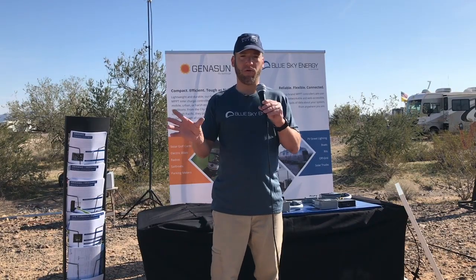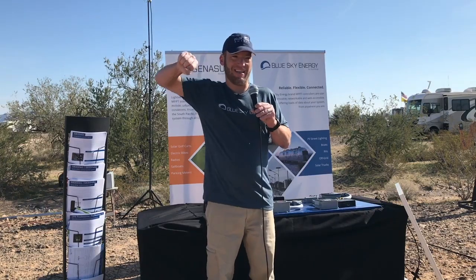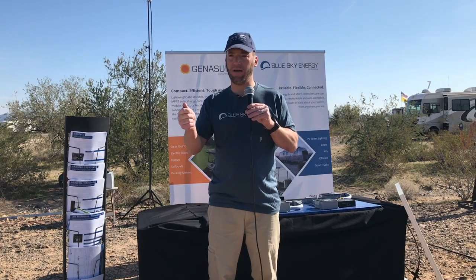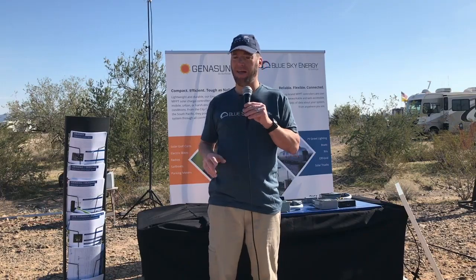My personal favorite is the A-N-L style fuse, Alpha November Lima. They range in quality - you can spend $40 for a fuse and holder, or $12 for a fuse and holder. It's a fuse that tightens down with a bolt on either side, so there's nothing to wiggle loose, nothing to go bad. You have an eyelet terminal and a bolt - that's my preferred style fuse. They don't go bad, and they don't wiggle loose over time.